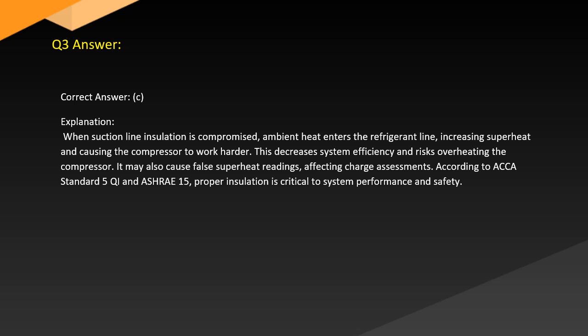Answer. Correct answer, C. Explanation. When suction line insulation is compromised, ambient heat enters the refrigerant line, increasing superheat and causing the compressor to work harder. This decreases system efficiency and risks overheating the compressor. It may also cause false superheat readings affecting charge assessments. According to ASHRAE Standard 15, proper insulation is critical to system performance and safety.